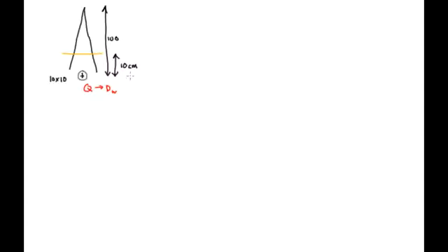And by the way, for a full TG51 measurement, it's done in liquid water, although you can do it more frequently in plastic. So then the dose to water is the charge times some calibration factor, N dose in water, N_D,w. That's how it's called. Okay, so I'm actually going to change the symbol here. Instead of writing Q for charge, which we normally do, I'm going to write M. So M is the meter reading on your electrometer. That's the common symbol.